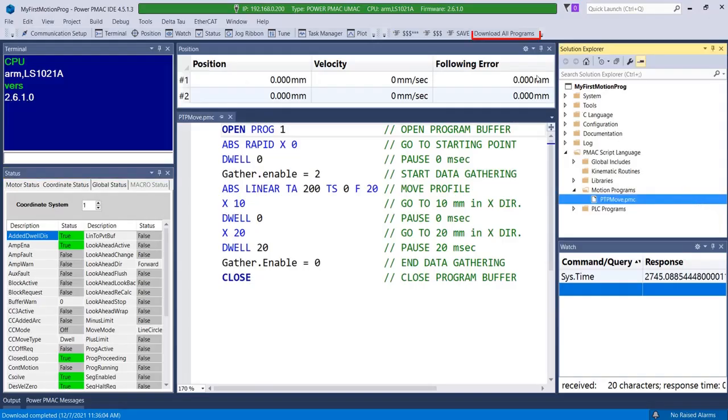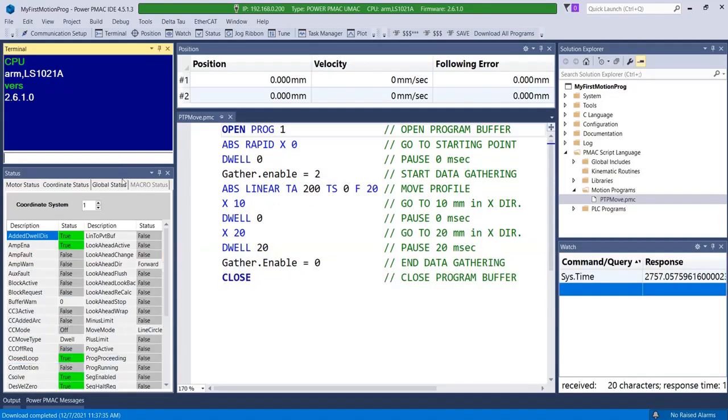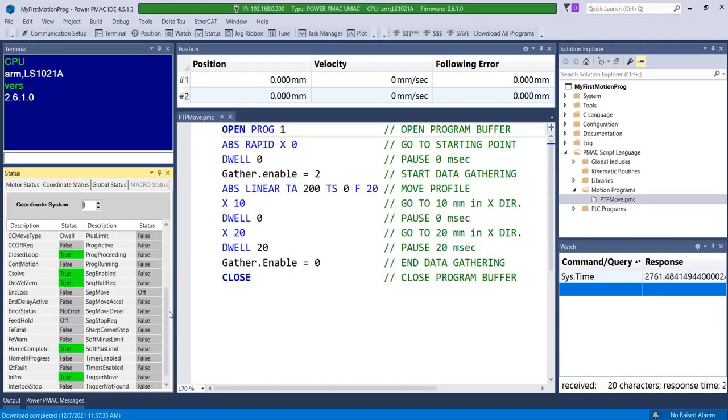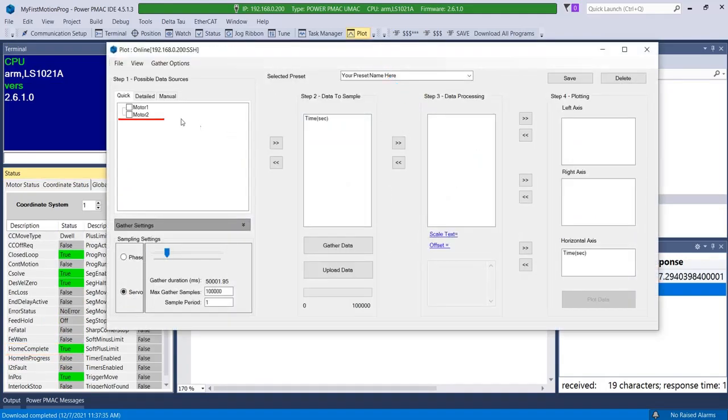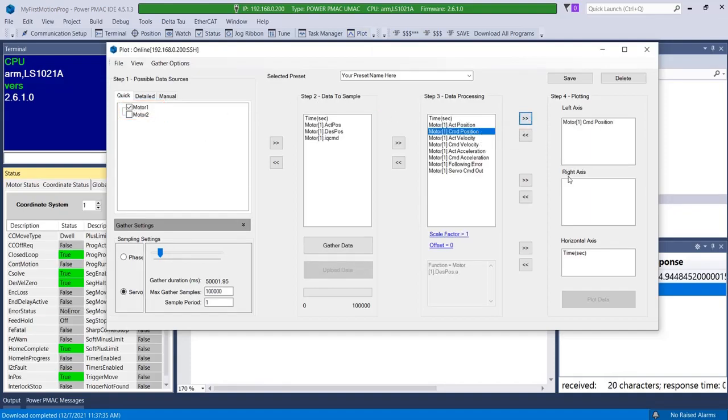Before I can run program 1, I must first download it to PMAC. After ensuring the download is successful and has no errors, check the status window to see if the motors in your coordinate system are in closed loop control and homed. With the motors ready to go, I can now open the plot tool and place motor 1's commanded position in the left axis with respect to time on the horizontal axis.